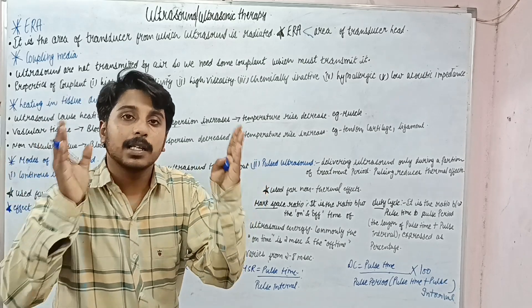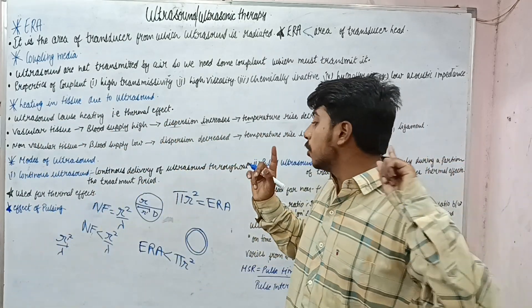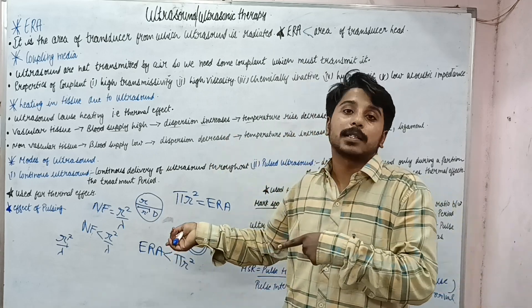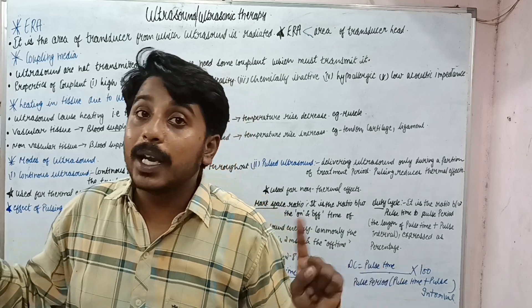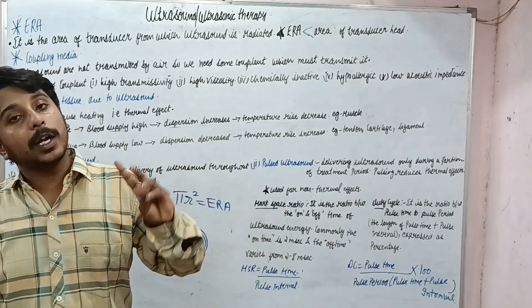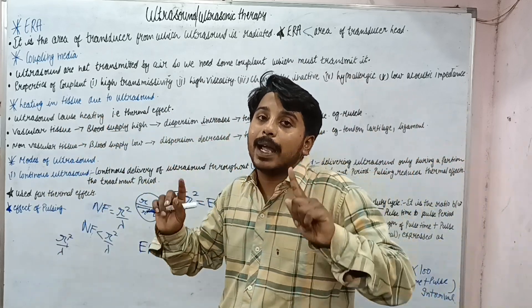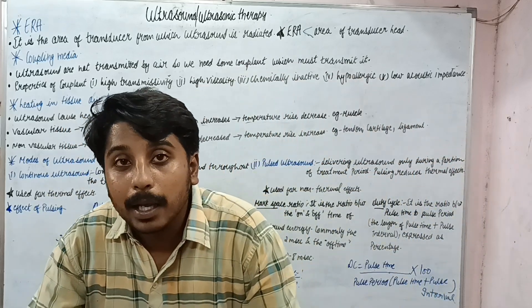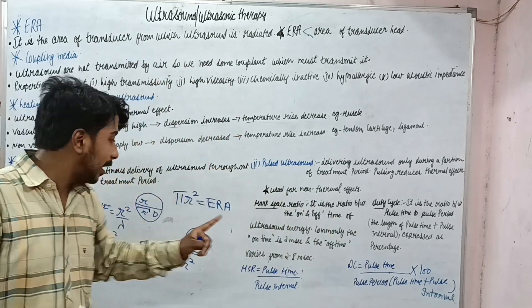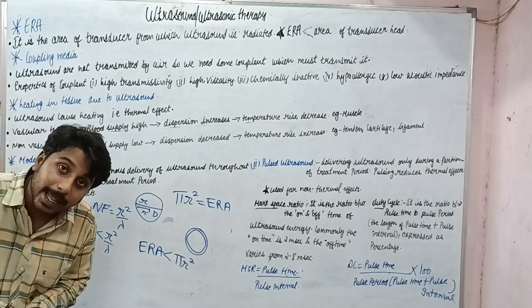The radius of emission is less than the actual radius of the transducer head. What you can measure with a measuring scale is the actual radius — you cannot find the radius from which radiation is actually occurring. So you calculate using the actual radius and note that the actual radiation area or near field is slightly less, which is why the less-than sign is used.